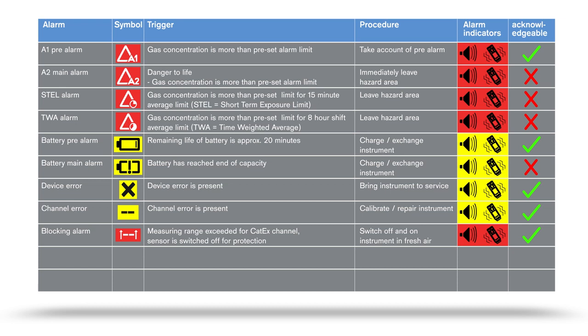For methane, the CatEx sensor offers the option of automatic range switchover within the range of 0 to 100 volume percent. In this case, there is no blocking alarm. This option is only available with the X-am 8000.